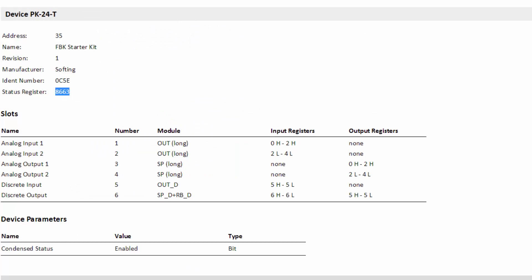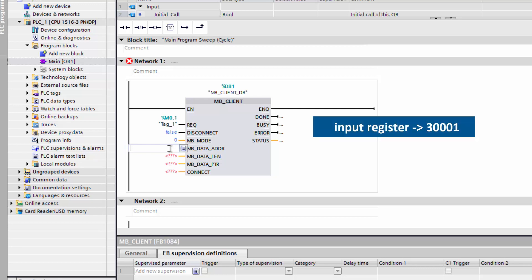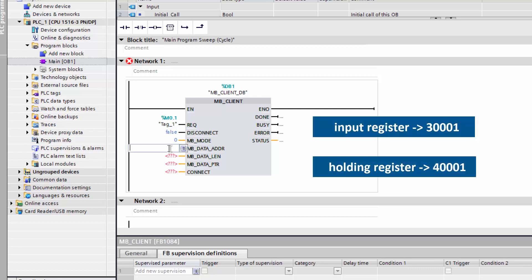The Modbus register specified in the report is a relative address. However, in the TIA Portal, you must enter the absolute address. The start register for input registers is 30001 and for the holding register 40001. You must therefore enter 38664 in the TIA Portal.